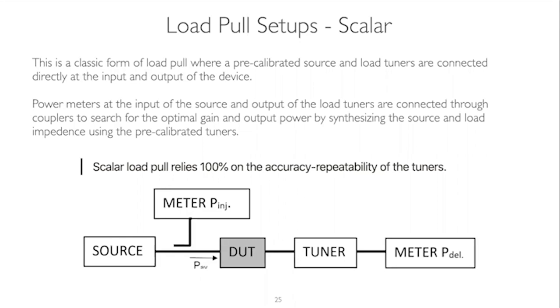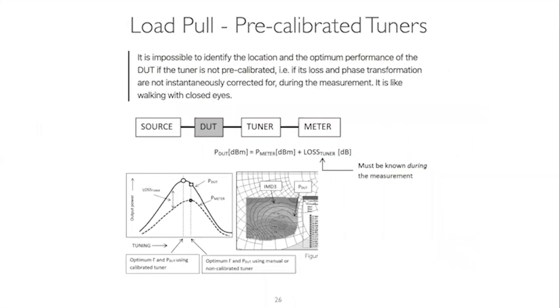You might be at a low loss point, therefore the power meter shows high power, but in reality it's not really the best point. You need to tune a bit further, but now the tuner loss will increase, and that will kind of mask the output power of the device and trick you. This is what this curve is showing.